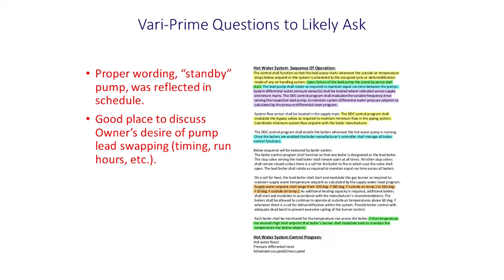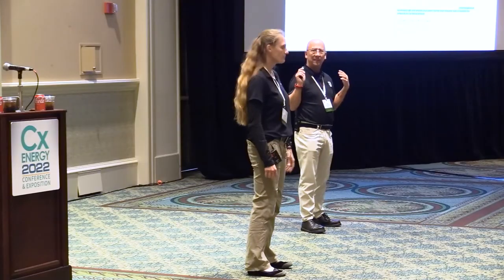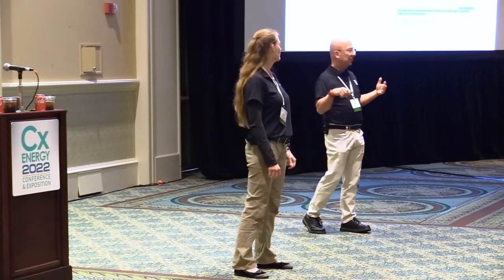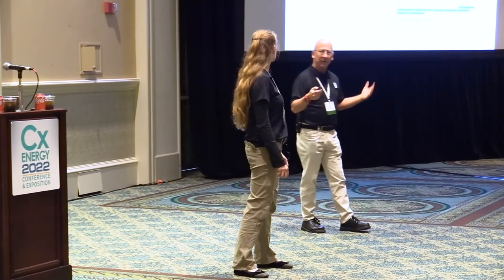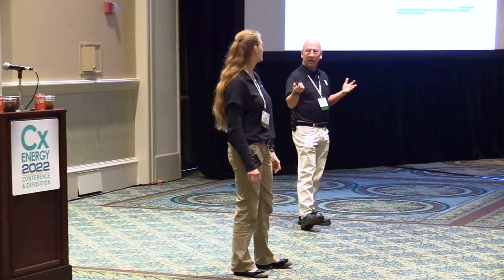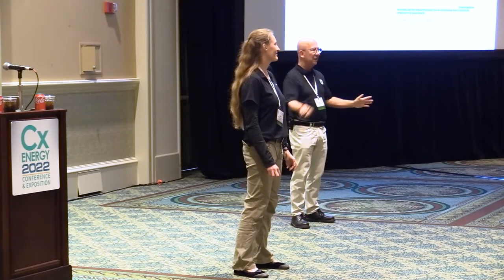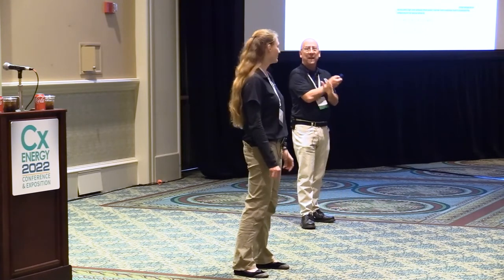And then this is a good place to actually talk about pump swapping. Is it going to be based on runtime? Sometimes it's just a generic runtime of, you know, 750 hours. Right. Again, in Wisconsin, we get a little nervous about that because with Murphy's Law, that means it's going to happen on New Year's Day at around 2 in the morning when it's like minus 15 degrees outside and we're making a decision to flop pumps. That would be a bad idea.